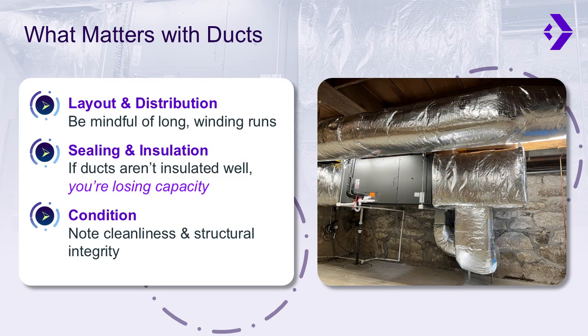Now let's look at the rest of the picture. How are the ducts physically laid out, and what condition are they in? Let's start with the layout and distribution. A heat pump needs a distribution system that delivers air where the load is. That means being mindful of long, winding duct runs. Long runs can result in decreased airflow and negatively impact distribution of conditioned air.